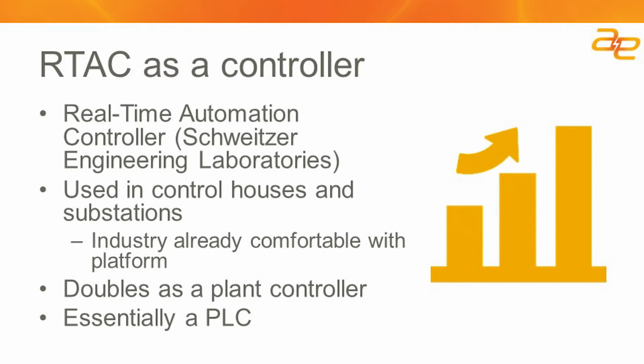So the product that we've used whenever we've done control systems for these QF sites, and sometimes when we do control systems for the larger sites as well, is a product made by SEL, or Schweitzer Labs. It's called an RTAC. They're very often used in large sites as an RTU, or a data concentrator. So it's a product that's well known and well accepted in industry, and it has the ability to do just about all of the types of control you can do with a PLC. It doesn't have all the interfaces that you would use in standard automation where a PLC would be appropriate, but from a functionality standpoint, it has all of the abilities to do ladder logic programming, function block programming, and structured text programming like you would have in a PLC. So it's a data concentrator, but it can also be used as a plant controller at the same time.